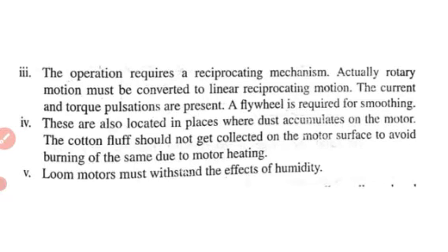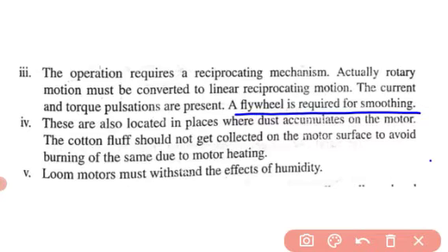The operation requires a reciprocating mechanism. Rotary motion must be converted to linear reciprocating motion. A flywheel is required for smoothing. I will discuss these flywheels later. Looms are also located in places where dust accumulates on the motor. The cotton fluff should not get collected on the motor surface, to avoid burning due to motor heating. Loom motors must withstand the effects of humidity.